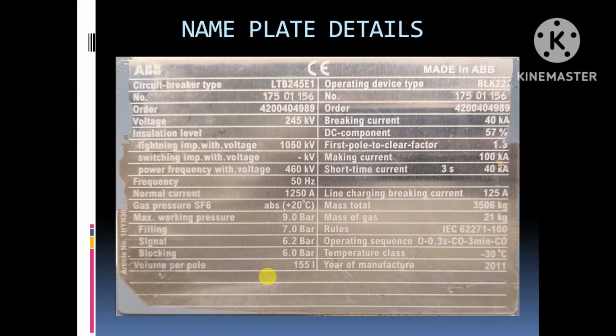So the discussion we are doing in this topic is SF6 circuit breakers. We have taken an ABB make LTB 245E1 model circuit breaker. It's called LTB, meaning live tank breaker, and it has a voltage range of 245 kV. It is installed in the 220 kV substation, but the highest system voltage can go up to 245 kV, so it is designed for 245 kV. So these are the SF6 gas specifications. What are the filling pressures, all these things are mentioned here. The power frequency withstand voltage is 460 kV. Breaking current is 40 kiloamps, making current is 100 kiloamps, exactly 2.5 times the breaking current.